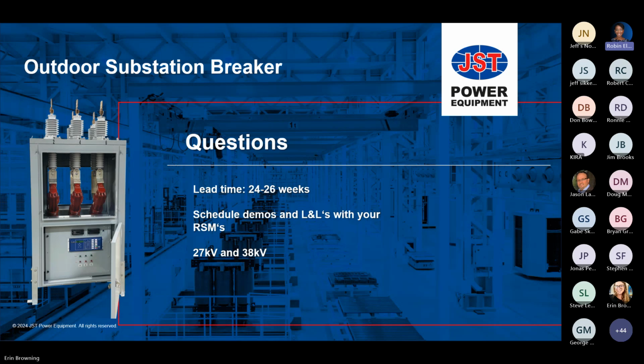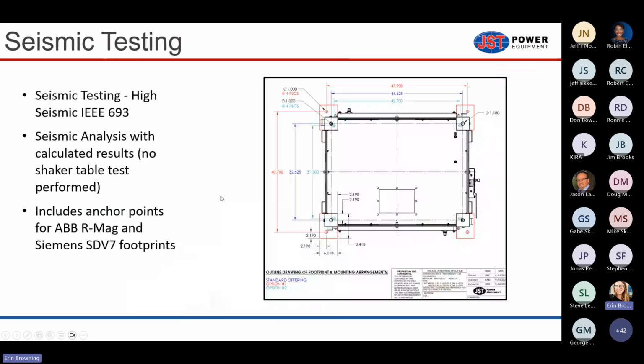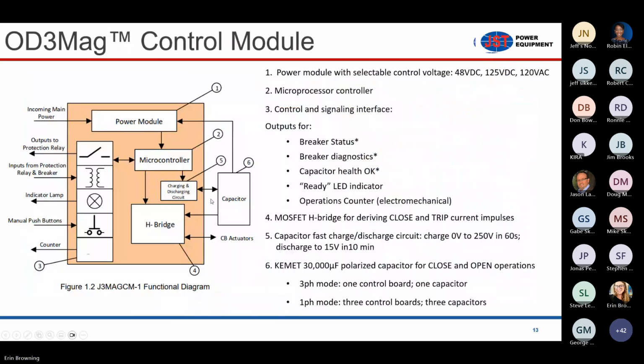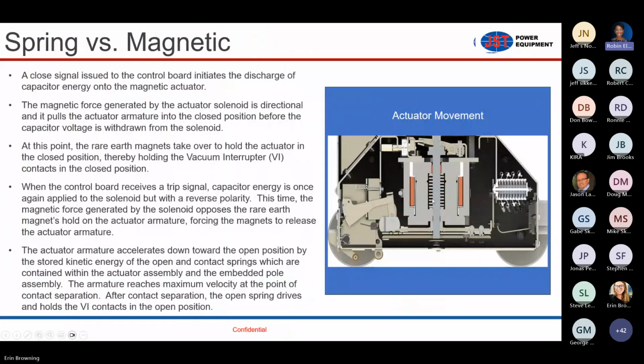One question from Lisa was, does the spring lose tension over time, which would cause the breaker to open more slowly? Our spring, the little spring that I showed in the graphic. Is that the spring you're talking about, Lisa? Or are you talking about in a traditional spring mech breaker? I'll answer both. So in the magnetic actuator, I showed you guys that there's this little internal spring. Right here, there's a spring.